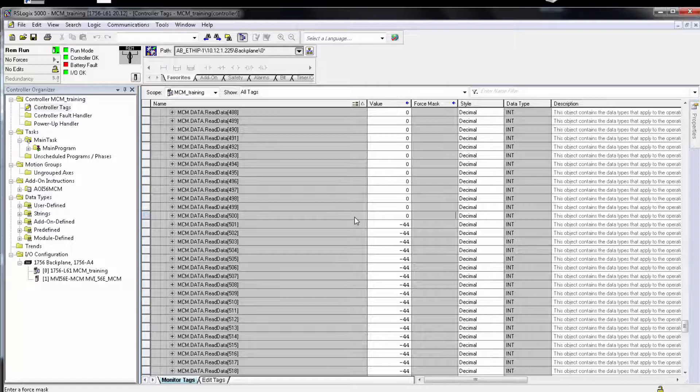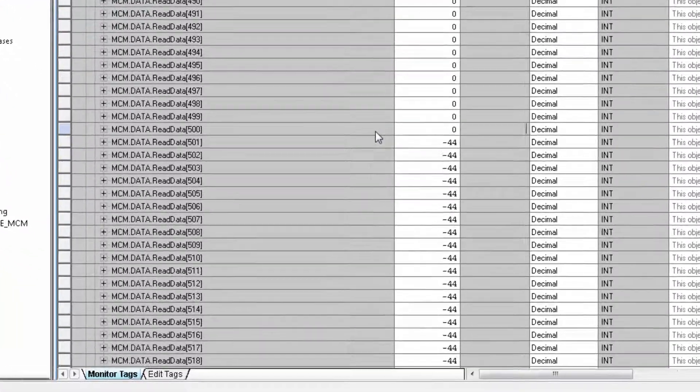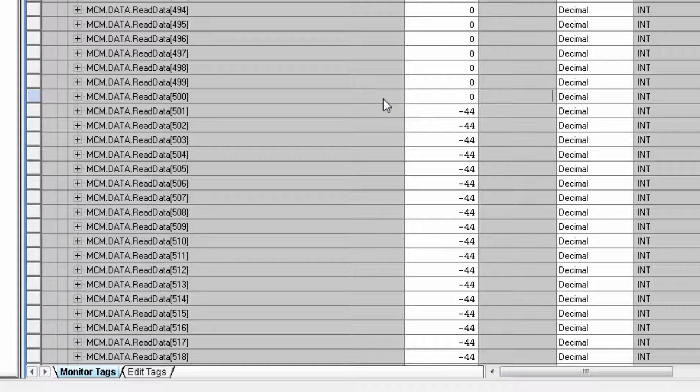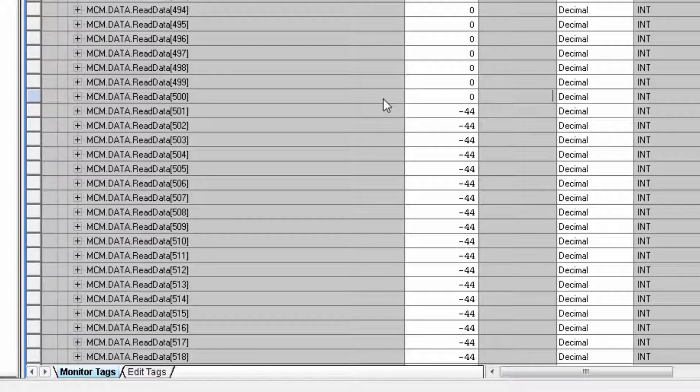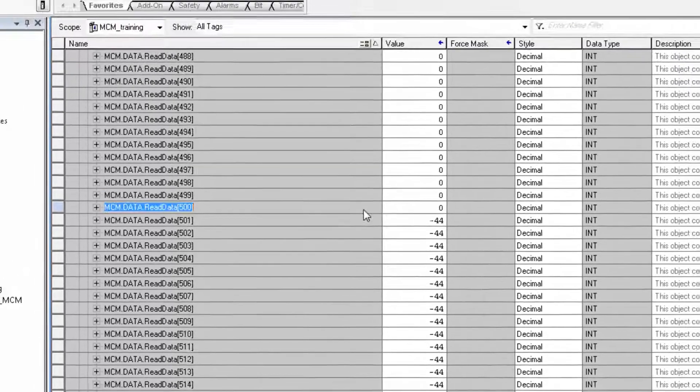The negative 44 errors that we see here for the rest of the commands are actually due to the register count being set to zero for all of them. And this is just because they haven't been set up and zero is the default value. So don't be dismayed if you see this in your command error pointer section.